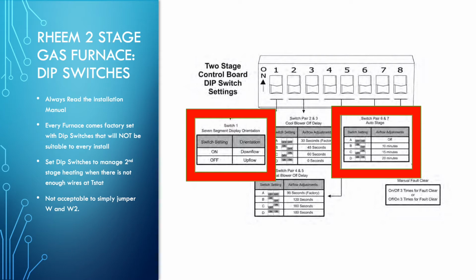So the key message on this particular slide is read the manual when you're doing installation. If you're in the field, when you're doing a tune-up on a system, especially if it's a follow-up tune-up, say a year later or 6 months later on a system we had installed, technicians need to grab the manual, open it up, verify dip switches to make sure they're all set properly.